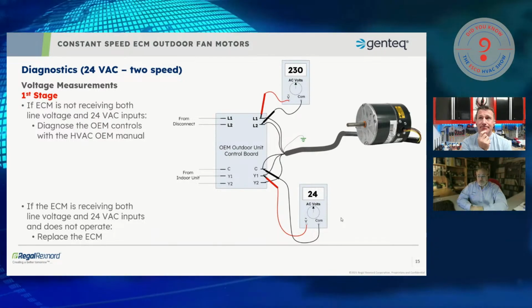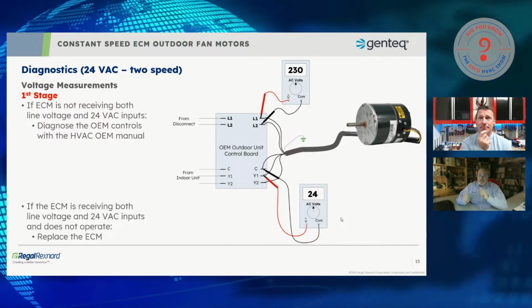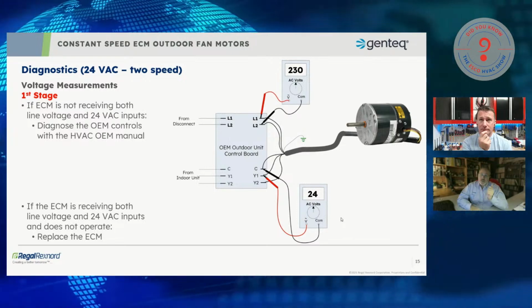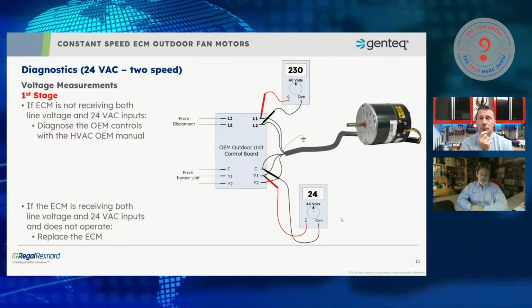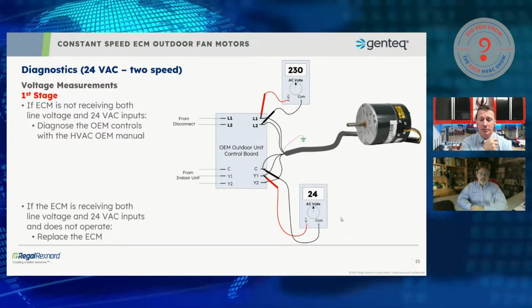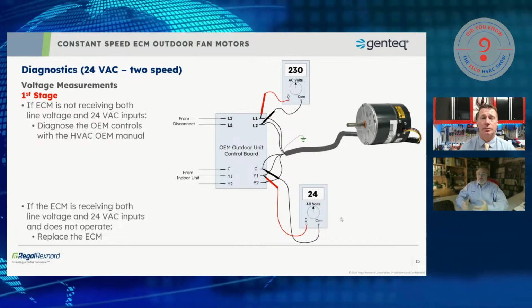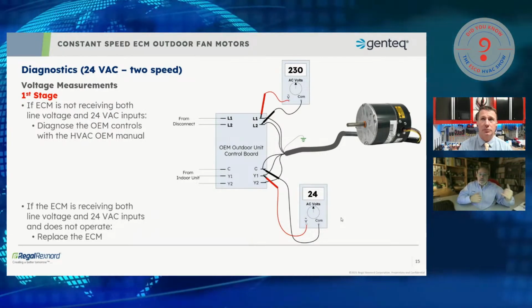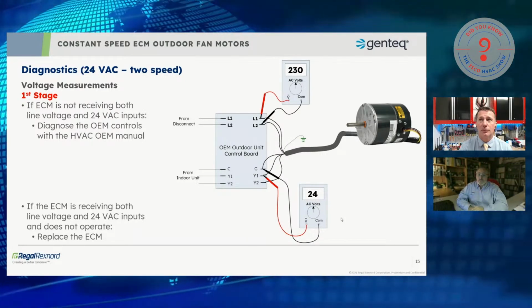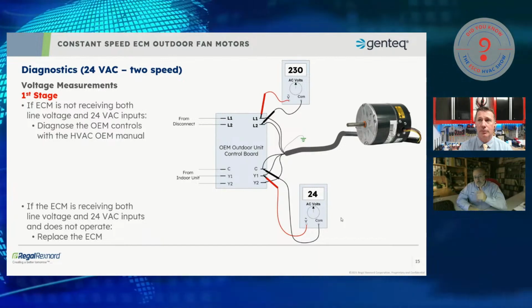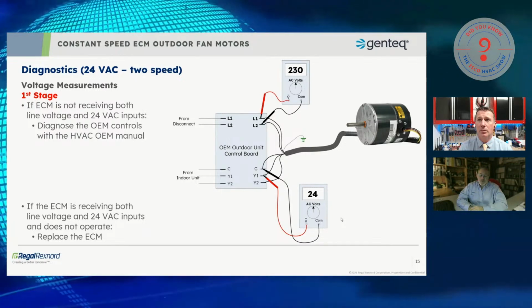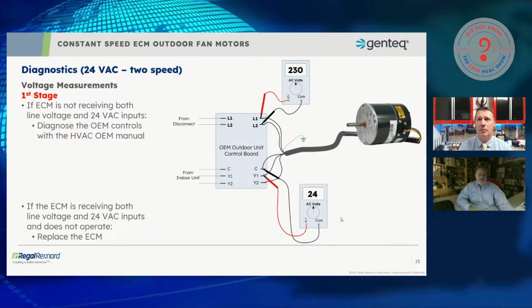If I'm stuck in the first speed operation, but I'm in second stage compressor, that's like having a really dirty coil. Absolutely. You might be trying to diagnose it with refrigerant or airflow through the coil, and it could simply be you're not operating in second stage speed on the motor as well. So if you have anything to add to that, please feel free.